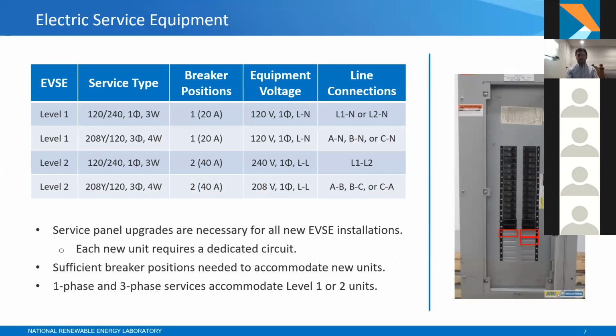But really, I've summarized all that in this table here, sort of some installation requirements that you might be able to use comparing level 1 chargers versus level 2, and then say your typical home residential services like a 120/240 volts, or maybe a commercial 3-phase 208Y/120 volts. And in here we have for level 1, you can see here the breaker positions. That's sort of a requirement that you'll have for each of those breakers that you install. You need to make sure that you have spare positions for those branch circuits and the protective devices. I've highlighted those here on the right.